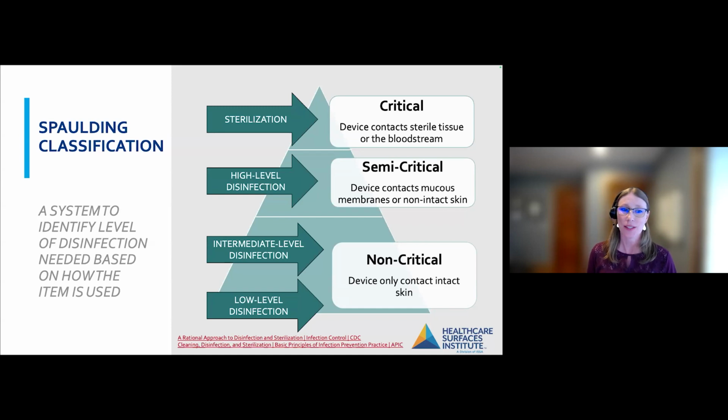However, as they're currently made, they cannot undergo the heat or the type of sterilization. There are multiple types of sterilization, but oftentimes those devices cannot undergo that level of sterilization safely without being destroyed. So as Linda was mentioning, we need to look at what surfaces make up those instruments so that they can undergo the highest level of disinfection possible.